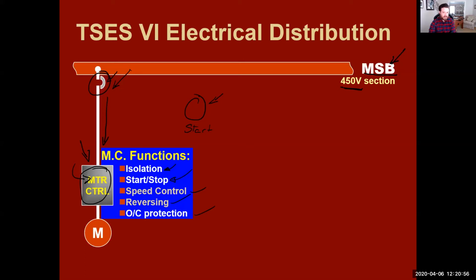So thinking of isolation, what else can we isolate, and how would we isolate it? We can isolate our start and stop buttons, our reset, our speed controller, our reverse option if we have one. But how would we isolate them? Would we have a push button with a long stick inside to isolate you from the actual start button, while still having 440 going through it? Is that what we're doing?